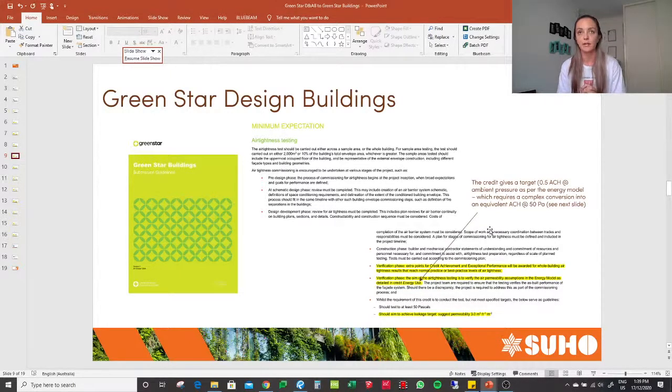And that is an important point, because a lot of the time the air infiltration assumptions in the model don't reflect what is built in real life at all. So there is a significant difference between what is modelled and what is built, and that's across the commercial and residential sectors. The energy model is there to be useful to professionals and builders. And so verifying the air infiltration levels in the model, in the as-built, gives the client a certain level of security around the end product.